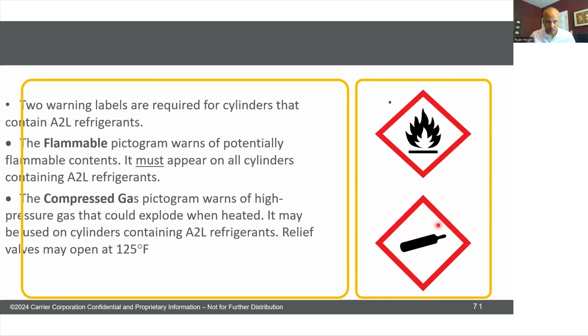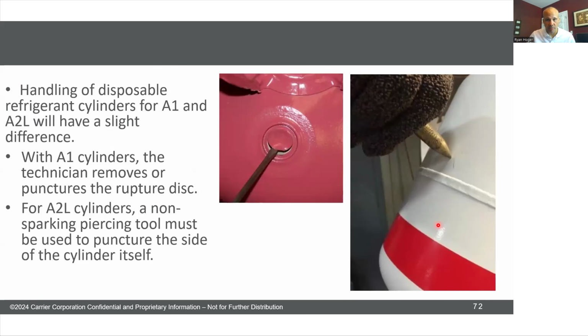All right, moving on. Cylinders are labeled. They've got little flammable diamonds on them because they are a flammable refrigerant. They've got the compressed air diamond on there like we had before. If you didn't know, you were supposed to pop out the rupture disc when you recycled one of these empty tanks. But now, because there is no rupture disc, they want you to, how do they word it? They want you to use a non-sparking piercing tool to punch a hole in the side of the drum.